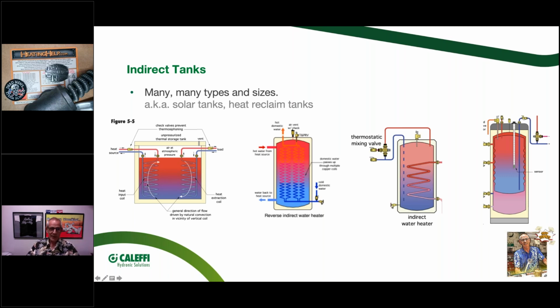So you're going to fill that tank up with tubing if you're trying to make a heat exchanger out of an insulator, which is what PEX tubing kind of is at the end of the day. It's not a great heat transfer material, but with enough of it, obviously we do radiant heat with it, so it can work.